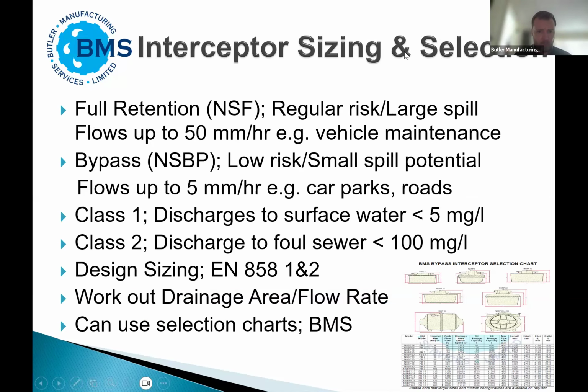Bypass interceptors are smaller, and the reason for this is that they're able to treat a flow of up to 5 millimeters per hour, and after that they bypass. That's why they're called bypass interceptors. This is where there's low risk or small risk potential of oil spills, such as car parks and roads. The idea being that if you have a dry period, 99% of the pollution will come in the first flush, and the interceptor takes it out, and then after that it's just surface water, which is fairly clean, to be discharged.